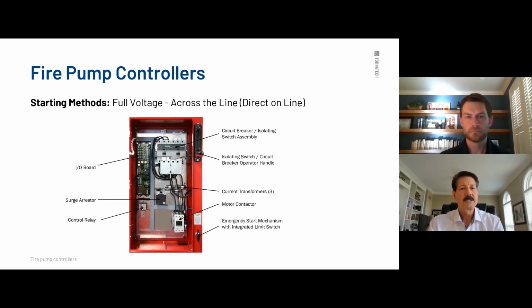Internal components, pretty easy. Come in the top, loop up into the isolation switch here. It loops around through the magnetic breaker only, down through the current transformers, which are sensing the amperage draw of the motor, to the contactor right here. And this contactor is the workhorse. I mentioned before, it's quite easy to size an electric fire pump controller. All we need as a manufacturer is the horsepower and the voltage. And all the work and calculations of all the components within this enclosure are done by us.